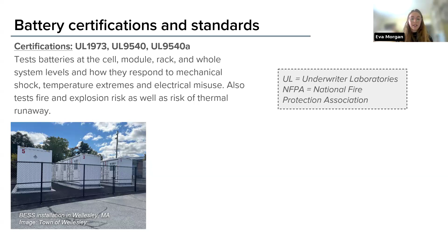There's also the fire standard, the NFPA 855. NFPA stands for National Fire Protection Association. This was created and adopted in 2020 and undergoes updates every 3 years, so the 2026 version just came out. It outlines design, installation, commissioning, operations, maintenance, and decommissioning of battery installations. It also outlines maximum energy and the necessary distance between packs, and the integration of different fire equipment.